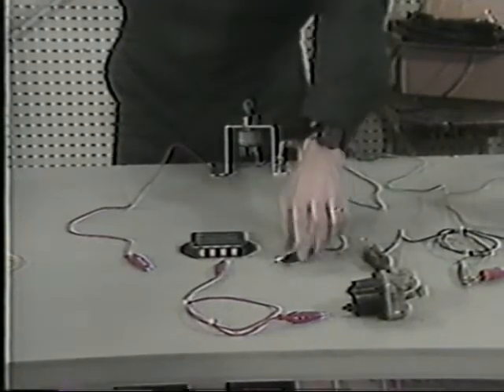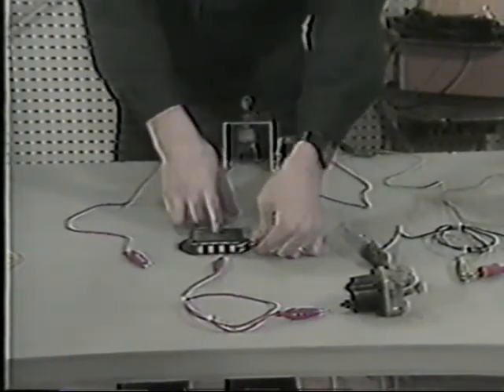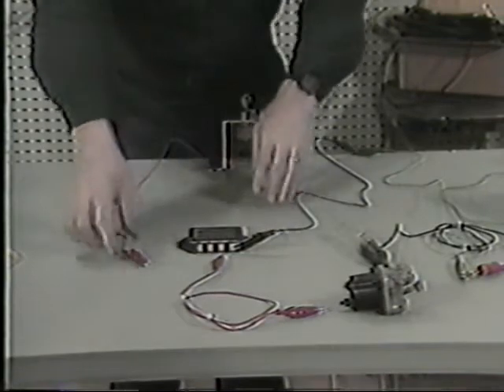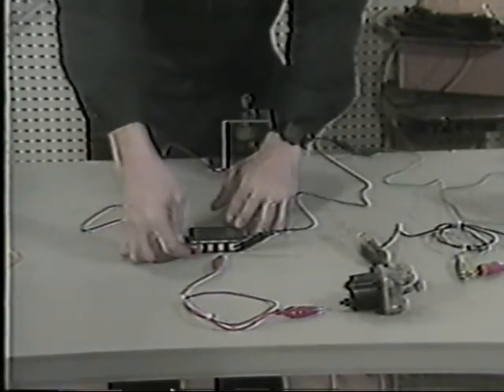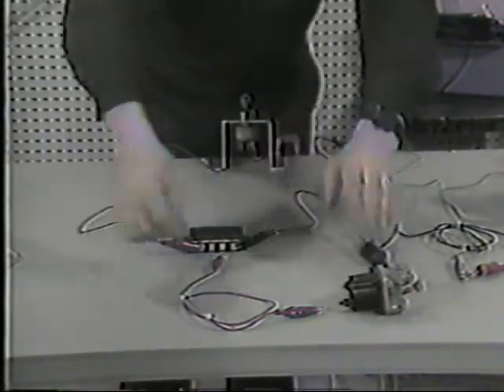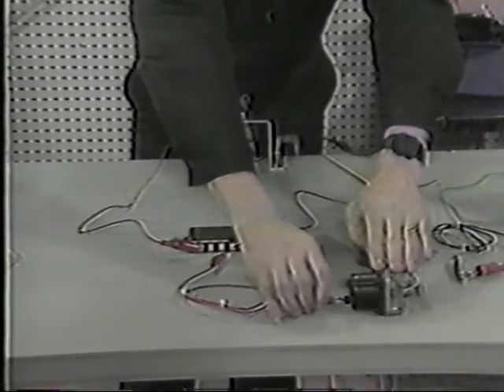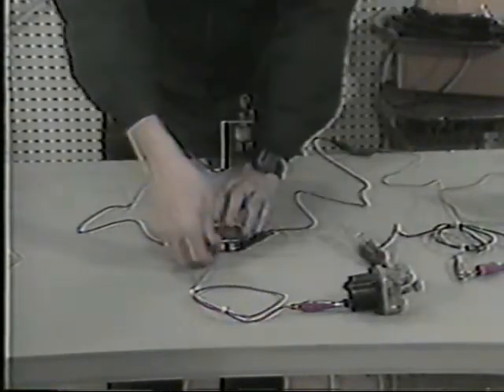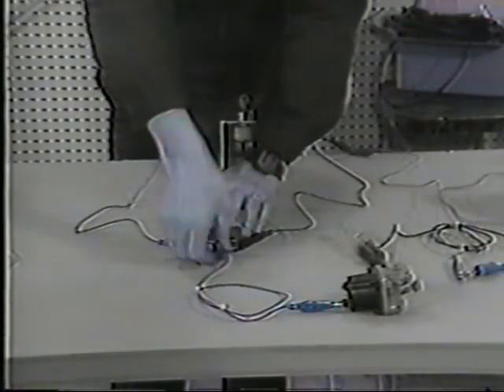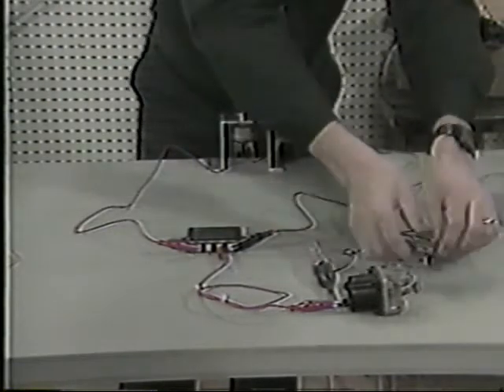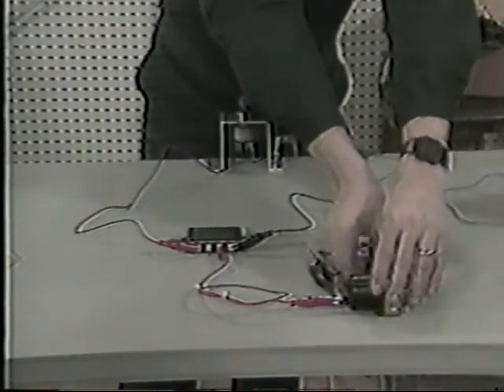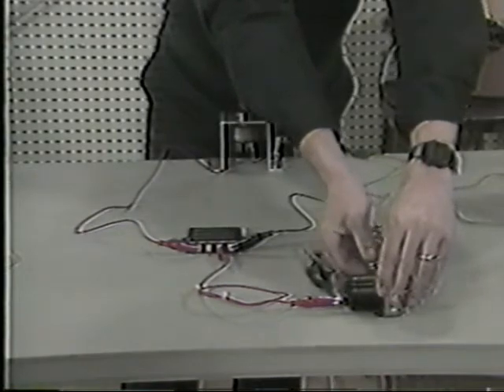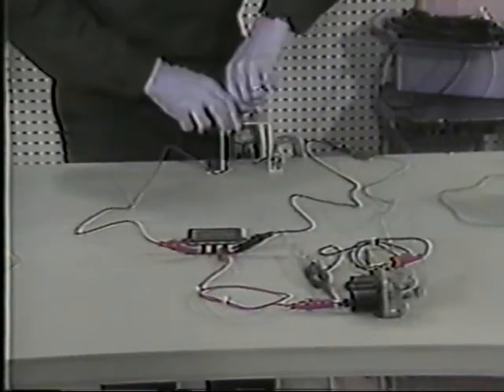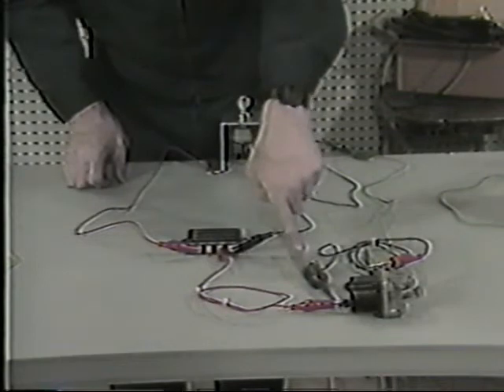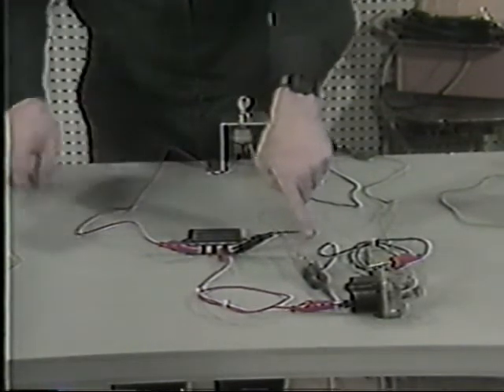Step number 1, connect battery negative to post number 4 on the module and connect your battery positive source to post number 1. Connect the fuel solenoid load to module post number 3. Connect your test light or voltmeter to the fuel solenoid load and make sure both of them are grounded. Turn on the power, and at this point there should be no voltage at the fuel solenoid.